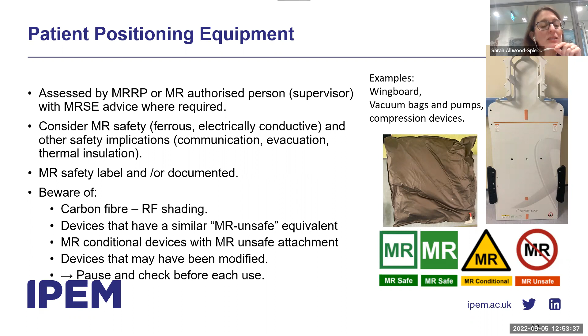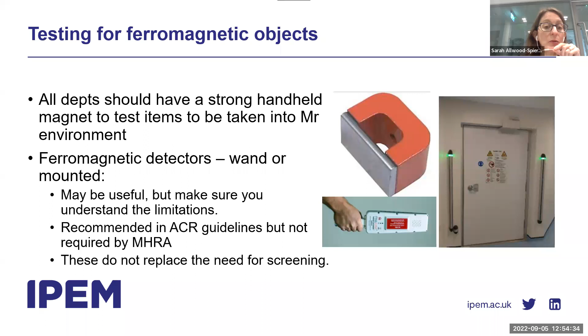Departments may also have a ferromagnetic detector, either a wand or a detector mounted on the walls. These are recommended in the ACR guidelines, the American guidelines, but are not required by the MHRA. They do not in any way replace the need for screening. They can be a useful adjunct as a kind of final check to catch anything that's still with the patient. So they may be useful, but it's important to make sure that you understand the limitations of ferromagnetic detectors. They don't catch everything, and you must be aware of those MR conditional devices that maybe have small ferromagnetic components. And you must have a process for how you're checking things if you are using a ferromagnetic detector.